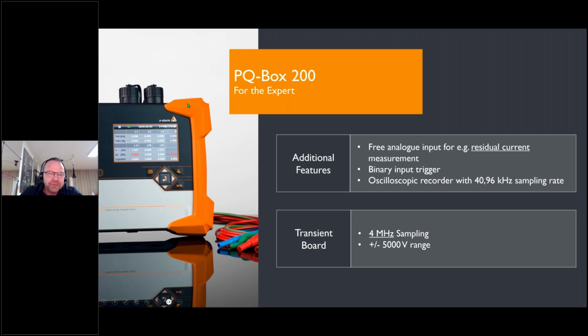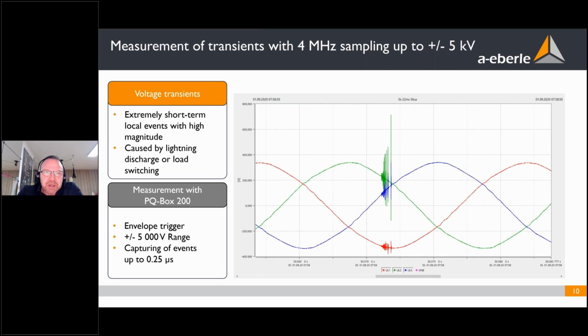The PQ-Box 200 is the fastest PQ-Box we have, for really fast transients. The sampling of the PQ-Box is 4 megahertz. And if you want to detect fast transients, which cause disturbance to your devices, then it's a must that the input range of the voltage channel is as high as possible. So we can measure transients of plus/minus 5,000 volts, up to 10 kV as the maximum range. Here is one application where we measure the transient on voltage L1 to L3 with a high sampling. If the sampling is high, it's easy to detect the maximum in the transient, the maximum measurement points.